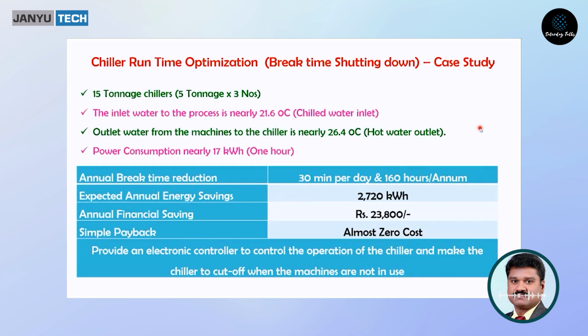My point is, for half an hour during both the morning tiffin break and the afternoon lunch break, the chiller keeps running for a full hour even though the machine is off - they don't realize it and don't switch it off. What we suggested is to install a simple timer: whenever the machine is off, the chiller automatically switches off, and whenever the machine starts, the chiller automatically starts. Or you can set a timer to start the chiller 2-3 minutes before starting the machine - that's enough, since the operating temperature is around 20 to 21 degrees, so the chiller can chill the water very quickly.